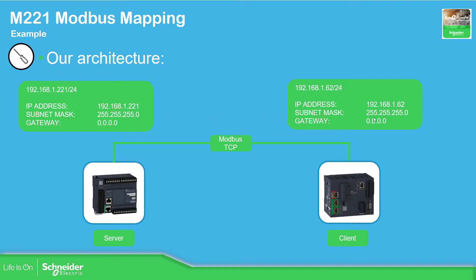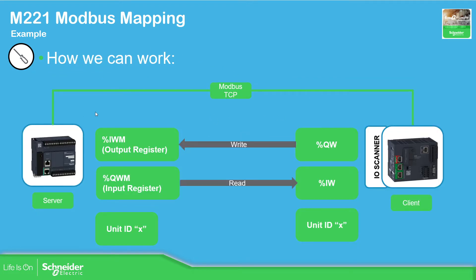You can see here the configuration I want for these devices. The idea of Modbus mapping is that once you enable it on the M221, it creates a different area — a %IW and %QW area — where another device can read and write information. Once this area is created, another device just needs to use a specific unit ID to access these registers. On the M262, I'm going to define the IO scanner using %QW and %IW, and I also need to add this unit ID, which must match the one on the M221 side.